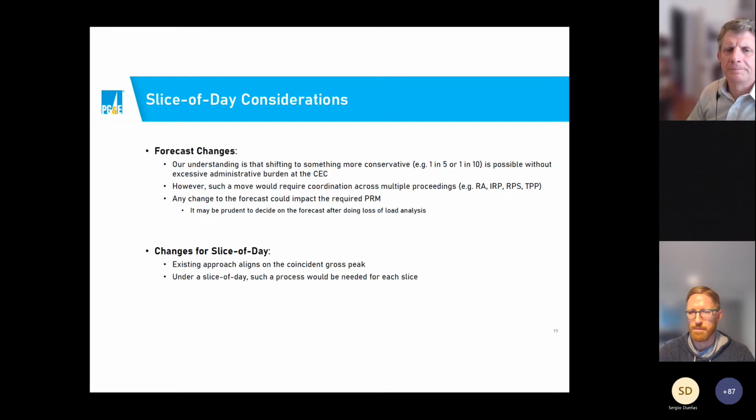If you were to weight more recent years more heavily or look more granularly in other ways at those trends, you do pick up accelerating trends in, say, cooling degree days that aren't necessarily reflected if you are just taking those 30 years of normalized weather data and using that for the draws in the LOLE analysis. The result of this is that when we're talking about the PRM, there is an element that we need to consider, which is what is that missing piece of climate impact?